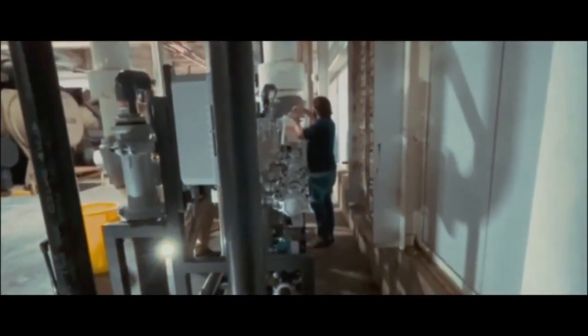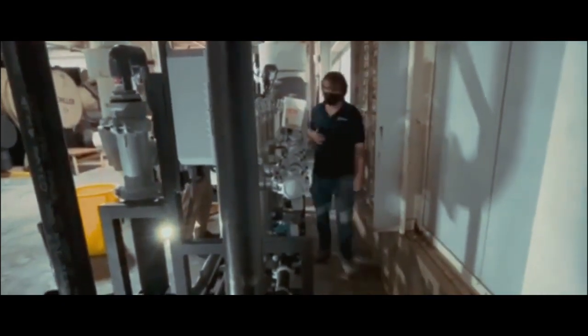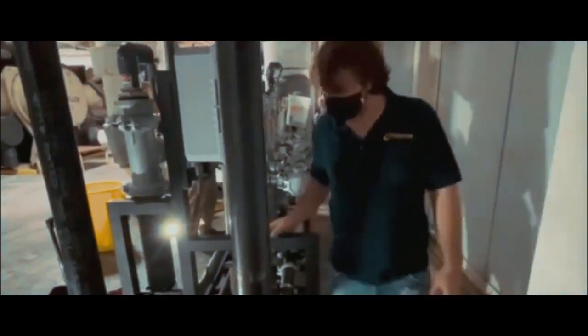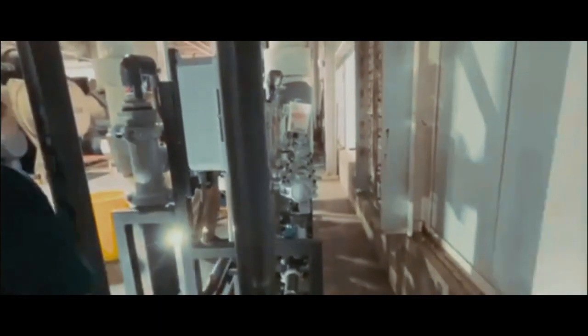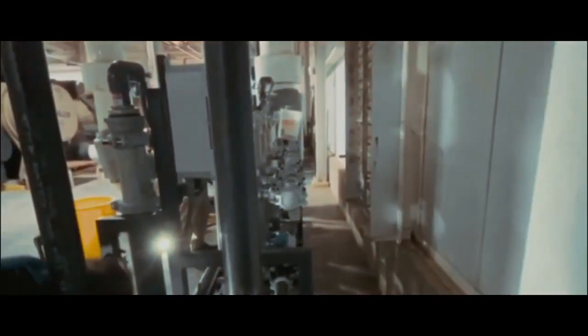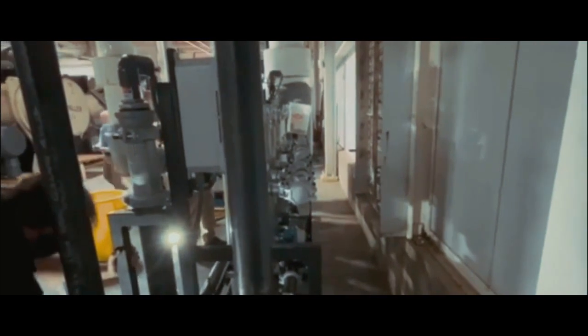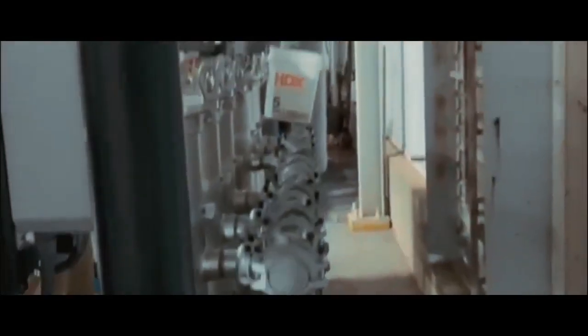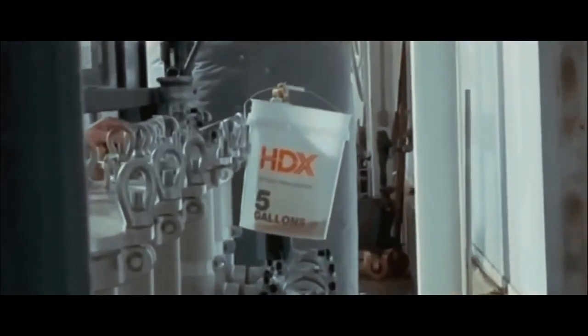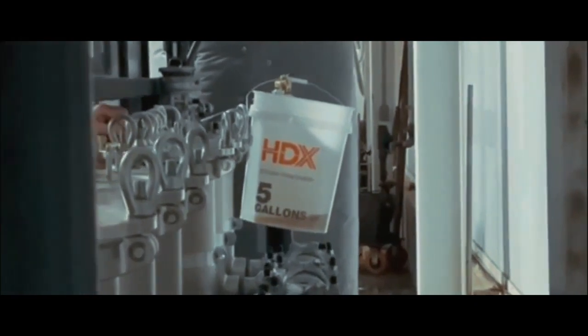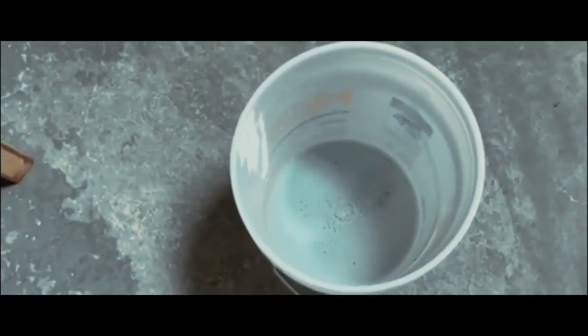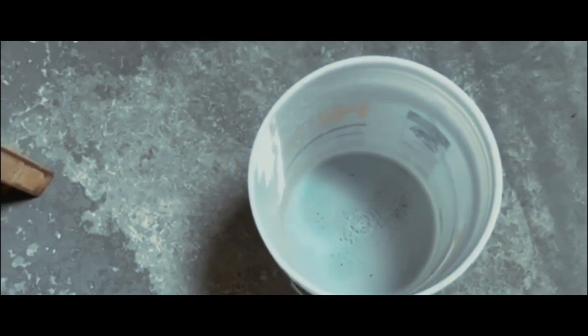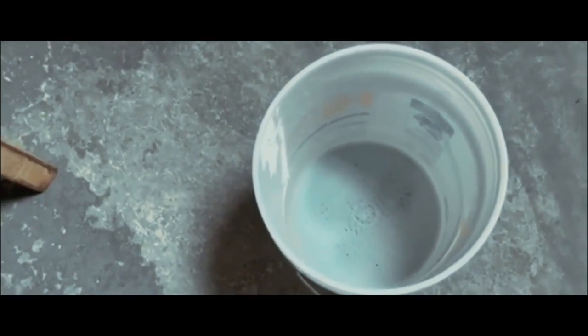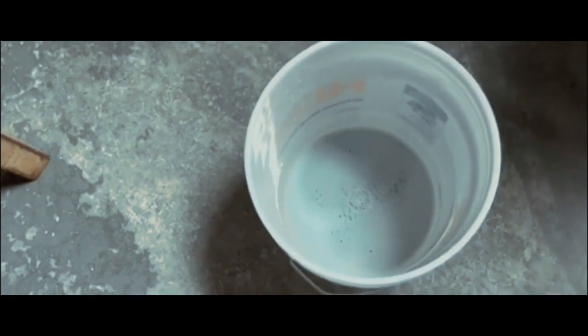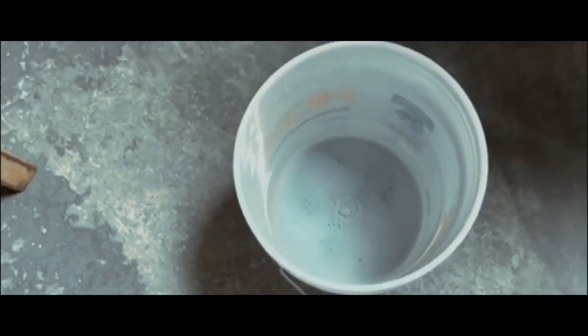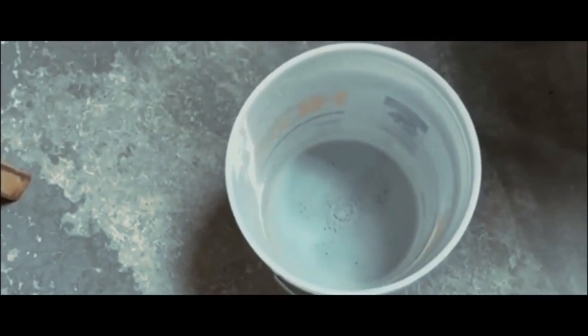After the ElectroCell systems are started up and running for about an hour, an initial water sample is collected in a 5-gallon bucket. This will be a baseline sample that will be used for a visual comparison test the next day. The clear baseline water will be compared to sediment collected in a static mixer after a 24-hour run period. The point of this test is to see how much sediment will be collected in the first 24 hours of running, if any. The initial bucket sample looks pretty clear, with little or no actual indication of contamination. Let's see what tomorrow will bring.